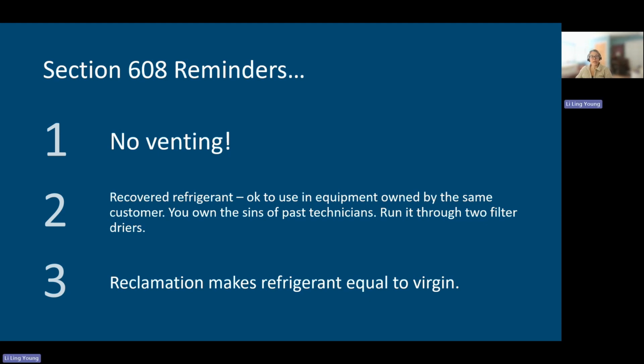Now I'm going to switch to talking about refrigerant recovery. And I'm going to start that out by just a few reminders from Section 608. One, there is no part of Section 608 that allows venting of HFCs. A de minimis release does not mean venting is okay. There's no venting that could be counted as de minimis.